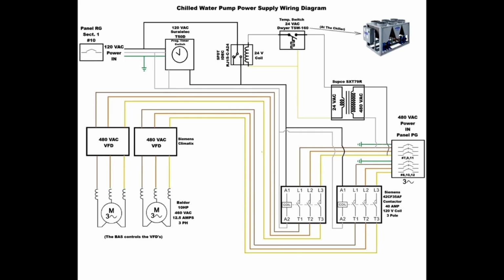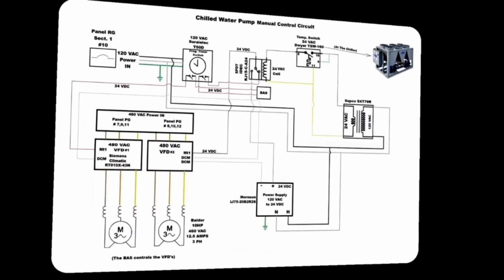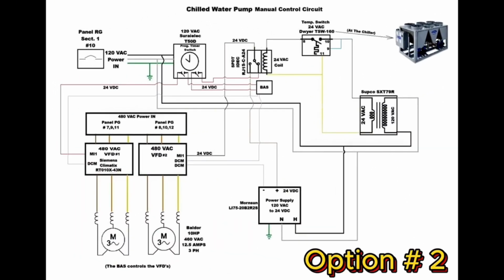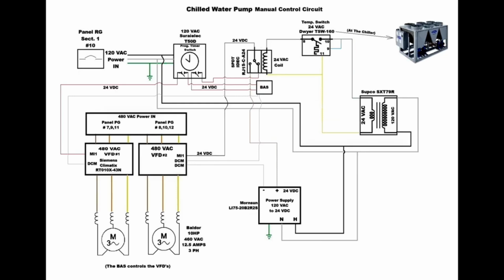As a safety, we also have, or are going to install, a temp switch up on the roof at the chiller, so during the wintertime, if it gets really too cold, that temp switch can also activate the coils on those contactors to run the chilled water pumps to circulate water, especially through the plate heat exchanger. Ultimately, here's what we went with. Much simpler, no contactors, no messing with the 460 volt wiring. We stuck with the 24 volt low voltage wiring.